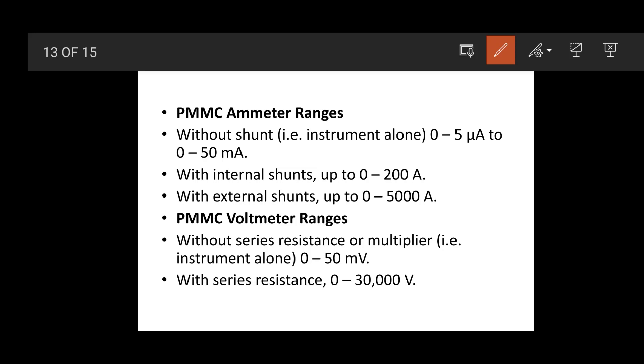PMMC meters are used for measuring current and voltage. The instrument can measure a maximum of 50 mA and up to 50 mV. To measure larger currents in real life, an external shunt is connected, allowing measurement over a wider range.